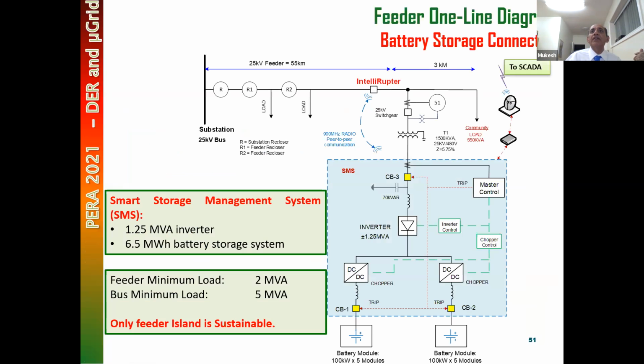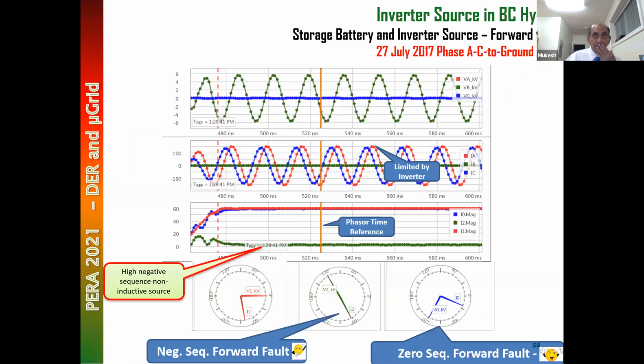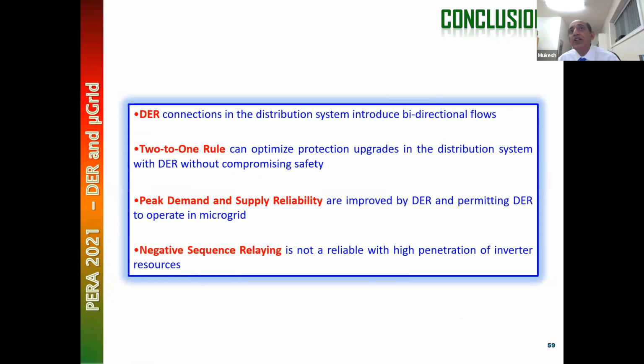So that's it. Basically, I'm coming to my conclusions. The conclusion is that distributed energy resource connections in the distribution system introduce bidirectional flows, and that bidirectional flow is not safe if we don't upgrade system protections. But if we upgrade protections like a transmission system, it may not be viable. The distributed energy resources become unviable. So the 2-to-1 rule can optimize protection upgrades without compromising safety, taking into account the size of a distributed generator. Basically, the larger the generator, the more upgrade; the smaller the generator, the lesser the upgrade.